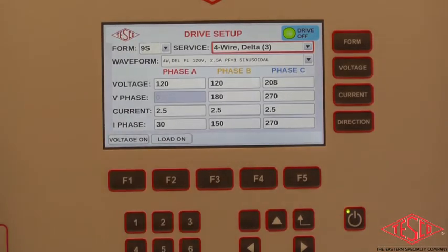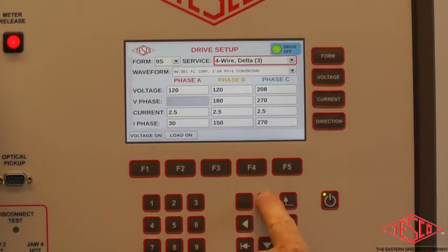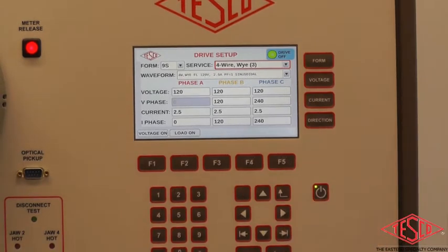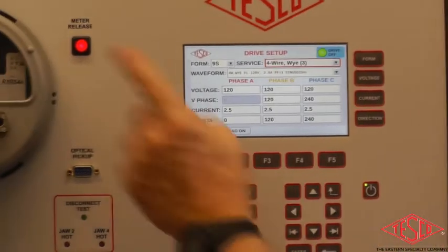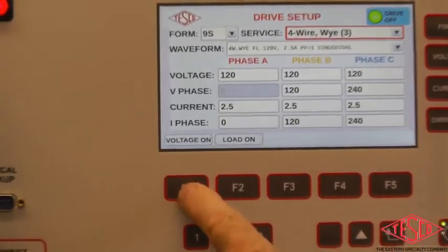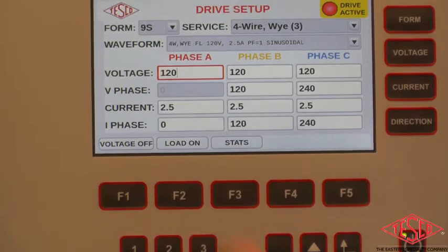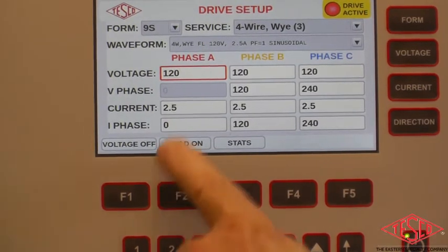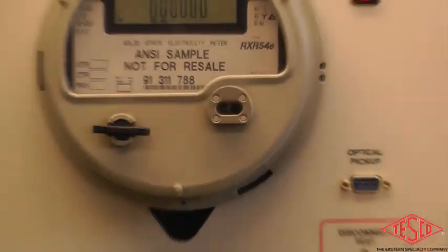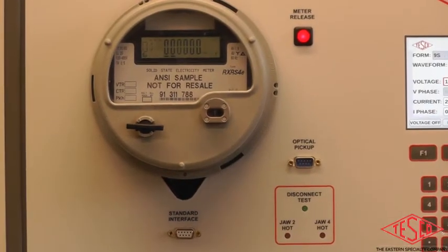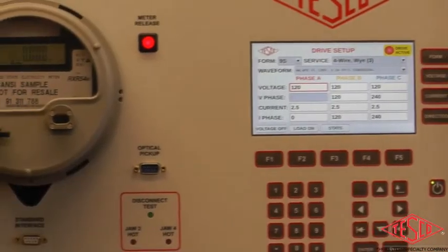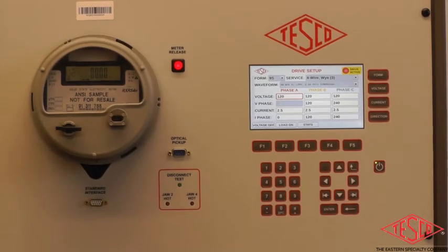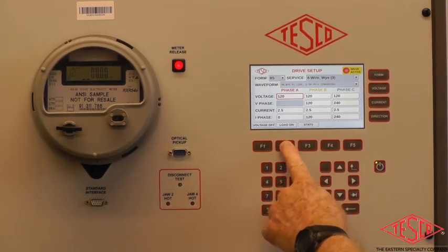And I will show you some vector diagrams that show you the different supplies and how they're configured, and this is all automatic. So by selecting a 4-wire Y, we can turn voltage on. This will turn only voltage on, and it'll turn voltage on all three phases. Voltage on. And now there's a load button. You can turn load on. Automatically, this is a form 9. It selects a transformer rated current of 2.5 amps. If it were a self-contained meter, it most likely would be 30 amps by default. So now I can turn load on.